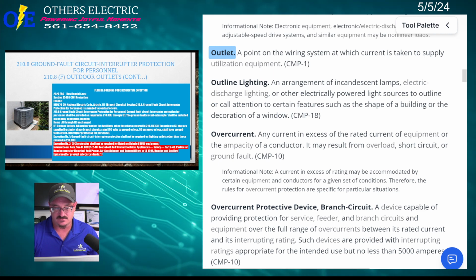Informational note: CSA/UL 60335-2-40, Household and Similar Electrical Appliances Safety, Part 2-40, Particular Requirements for Electrical Heat Pumps, Air Conditioners, and Dehumidifiers, or UL 1995, Heating and Cooling Equipment, product safety standards. So basically, here's the thing: the HVAC equipment doesn't meet the standard for GFCI protection. So if today you installed an outside condensing unit on a GFCI, like the National Electrical Code says is required, it would not run properly. It would trip.